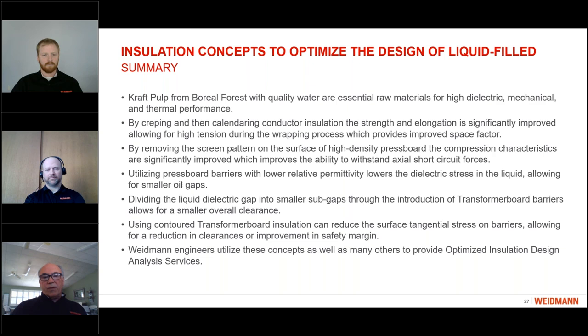So subdividing the gaps, using as thin of a board as you can, and then using that board if it's low density board, is the most optimal way to do it. And then there's another stress that the insulation designer has to consider, and that is the interfacial stress, the stress along the surface of the insulation. Jason also called that creep stress. And we see that most relevant at the end of the winding.